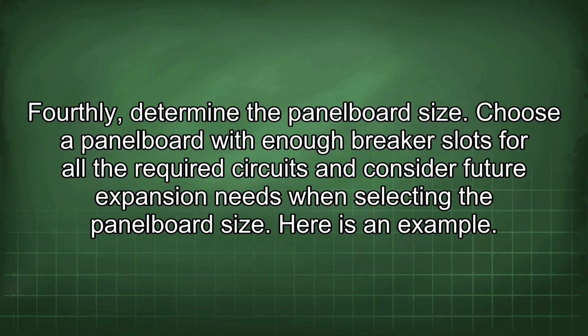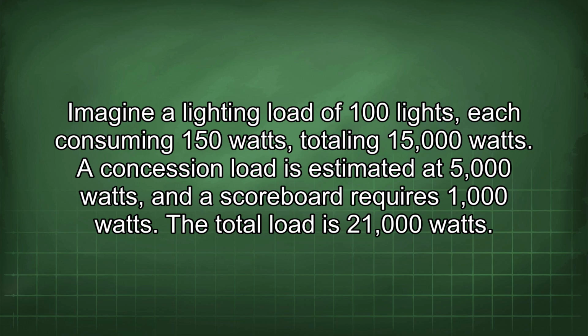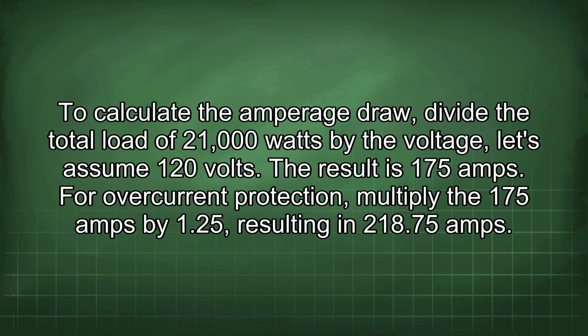Here is an example. Imagine a lighting load of 100 lights, each consuming 150 watts, totaling 15,000 watts. A concession load is estimated at 5,000 watts, and a scoreboard requires 1,000 watts. The total load is 21,000 watts. To calculate the amperage draw, divide the total load of 21,000 watts by the voltage, let's assume 120 volts. The result is 175 amps.